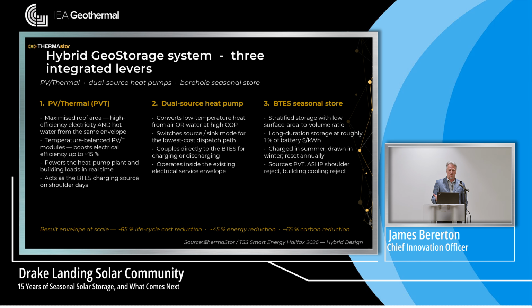So what are the levers we want to use in a hybrid geostorage system? You have to have a heat source. It could be PV thermal. Sometimes it's better if we use air source heat pumps. So depending upon your market, your tariff structure, if you have a flat electrical price, even if it's low, 8 cents, 7 cents a kilowatt hour, it's still better to use PV thermal because that waste heat is free and you're getting the electrical energy.